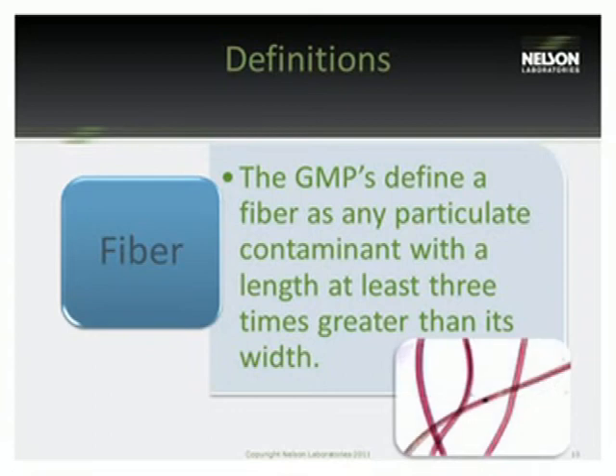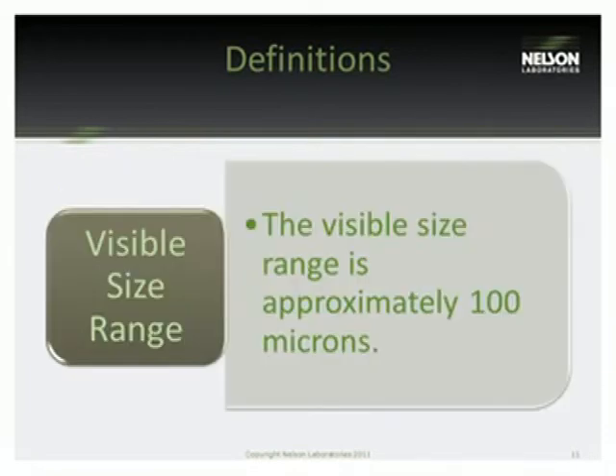So there's an example of a fiber, a red fiber. Sometimes it's helpful to try to characterize fibers and other particulates by color or size, or shape rather, in order to determine where in the process of either manufacturing, packaging, or handling a particulate may have been generated. The visible size range is typically regarded as about 100 microns. Some can see larger than that, smaller than that, and some can't see anything smaller than maybe 200 or 300 microns. But typically 100 microns is considered the visible range, and most of the time we're interested in particles below that range for subvisible particulate matter testing.